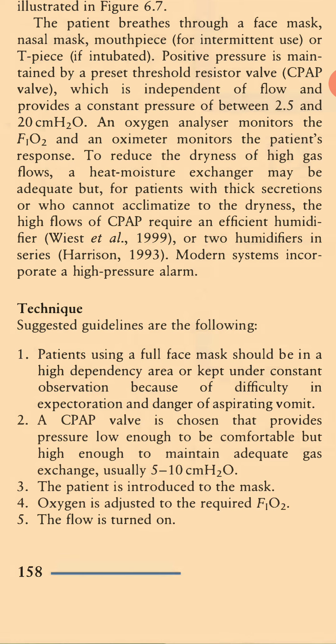The patient is introduced to the mask. Oxygen is adjusted to required FiO2. The flow is turned on. The patient assists with putting on the mask if possible in order to reduce anxiety. It is best that the mask is not strapped on until the patient has felt the flow and is ready. Flow should be at a level sufficient to maintain an open CPAP valve even during a deep breath.